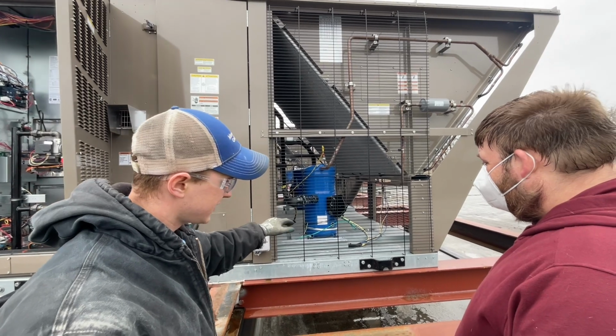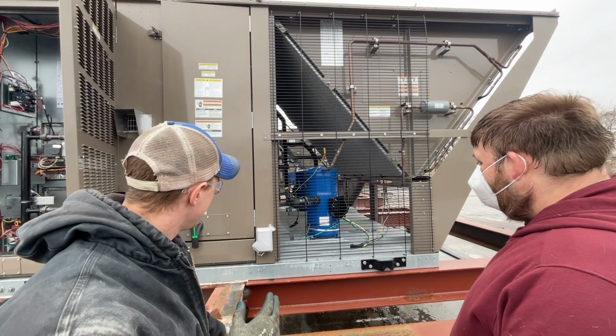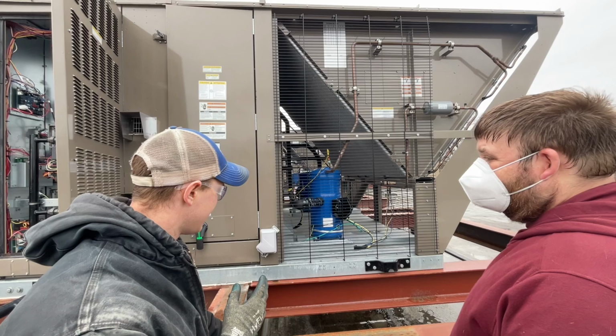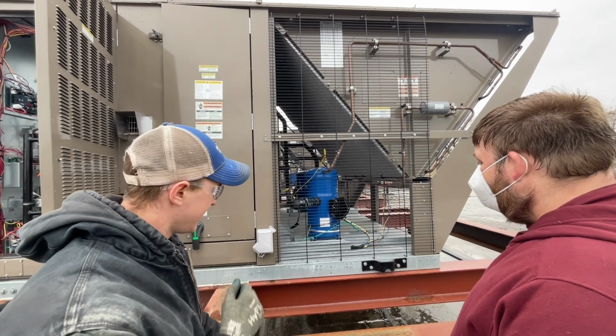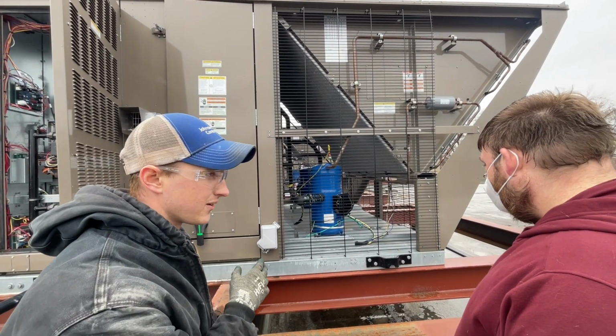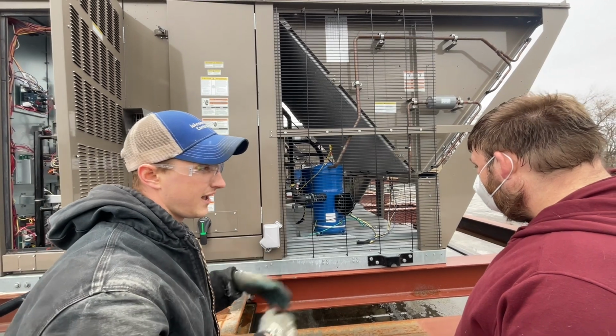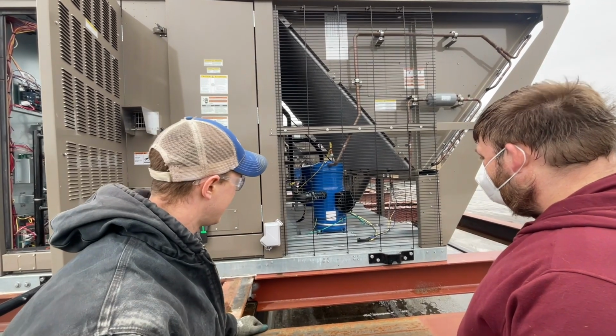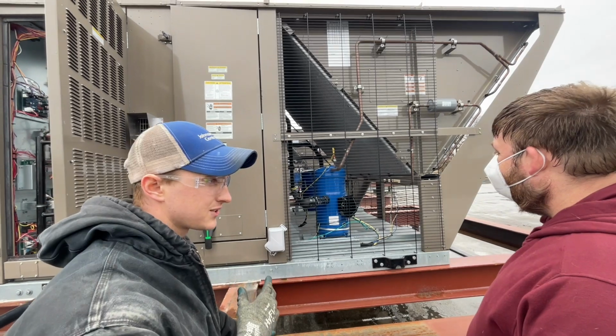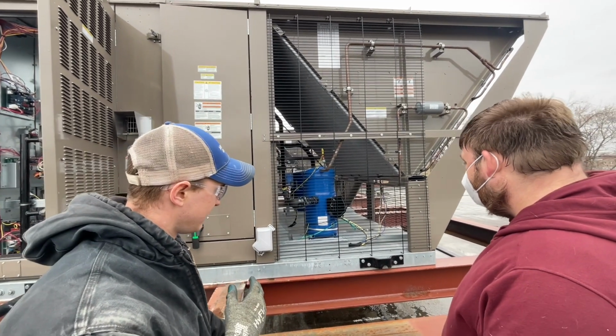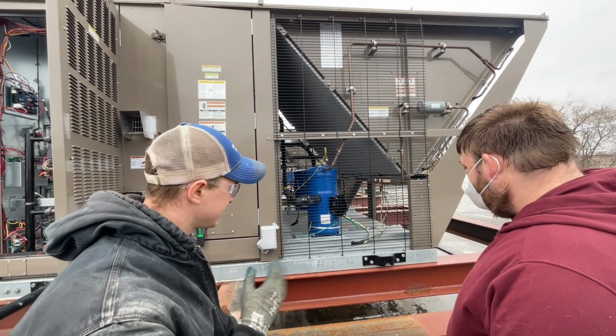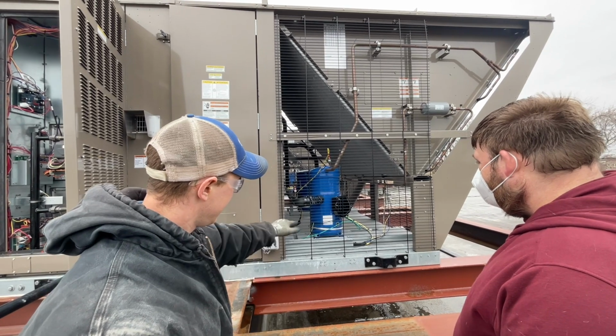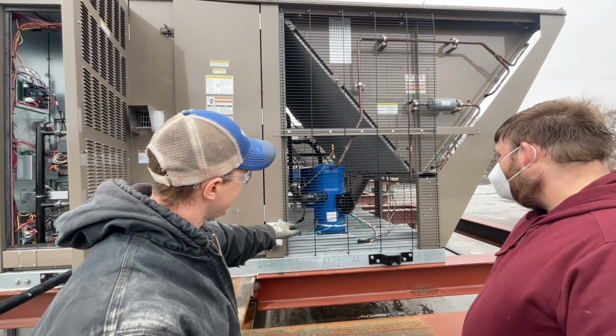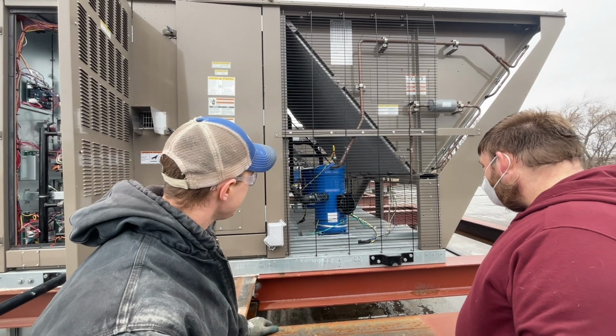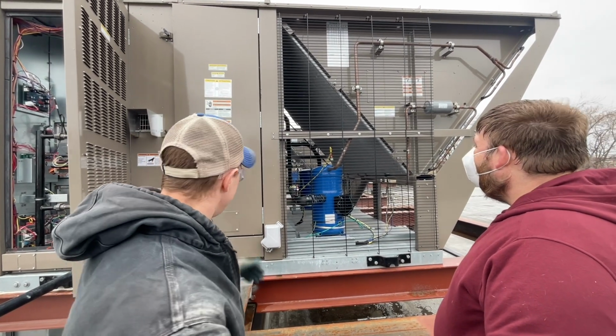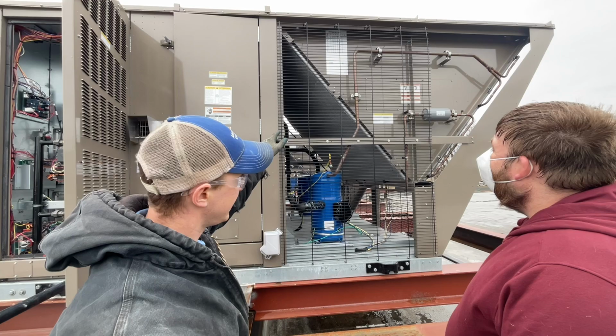So definitely make sure those heaters are always heated up, and if for any reason you have the unit off for, I believe they say over an hour, you want to have the heaters energized for 24 hours just to boil all that refrigerant out of there. It'll state that all in the manual, so definitely reference the manual. There's a ton of info in it, but that's one thing I would check if I were you, maintenance wise.